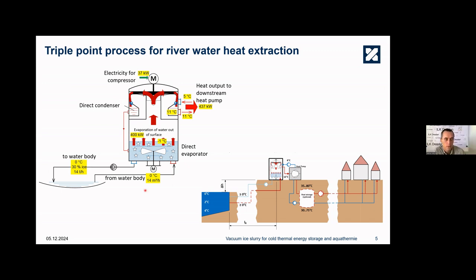You can see it quite well here with the temperatures. You can even use 0-degree water. You can take out of this water 400 kilowatts of heat, and you return the same mass flow, but with 30% ice, to the water body. Attached to this plant, of course, you need a downstream heat pump, which then generates out of this temperature level more or less every temperature level you need for your heating purpose.